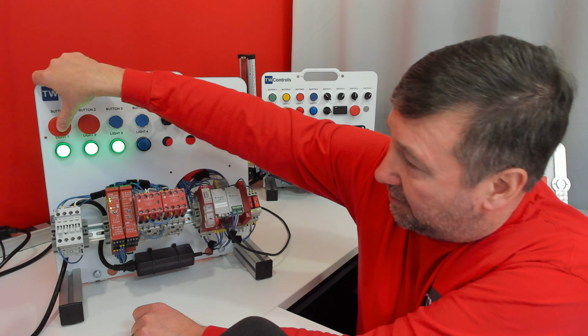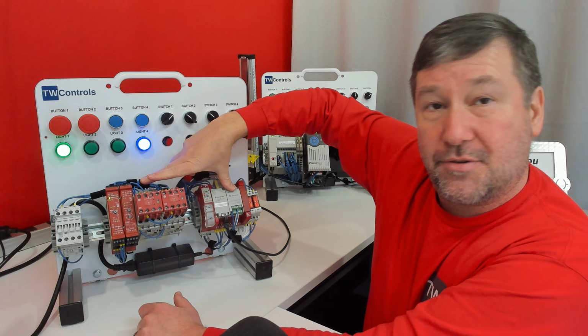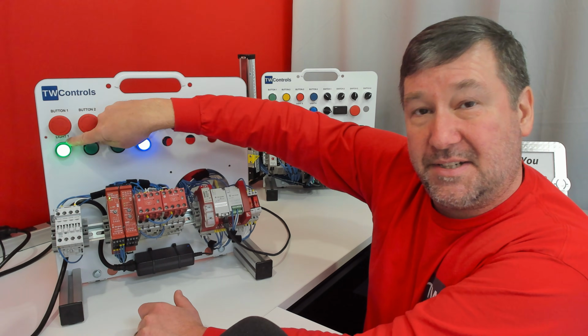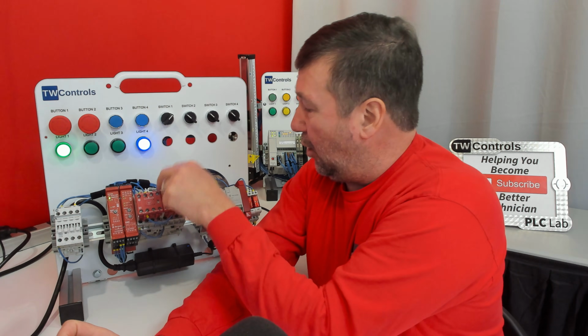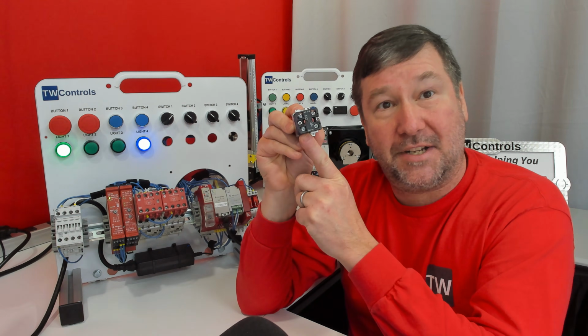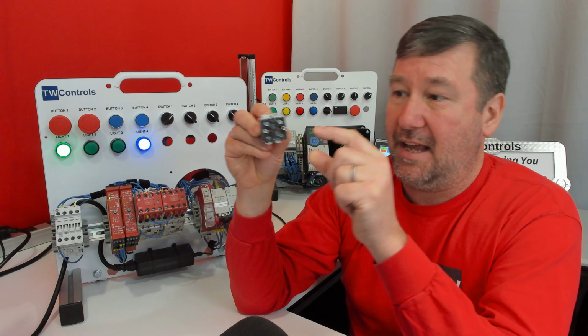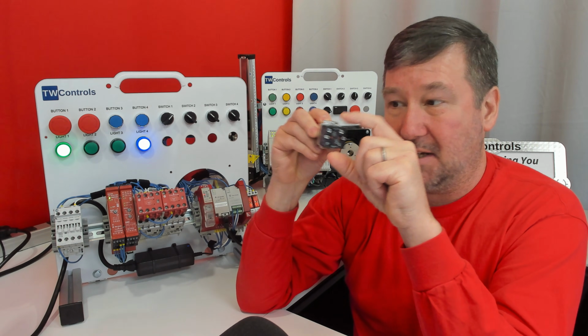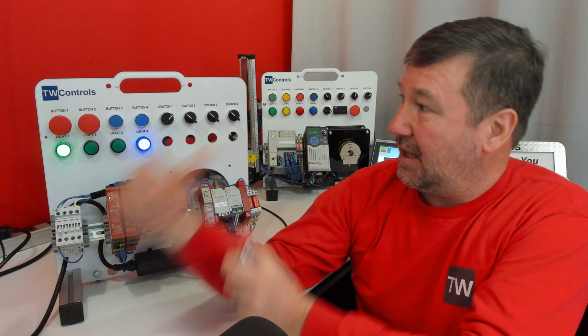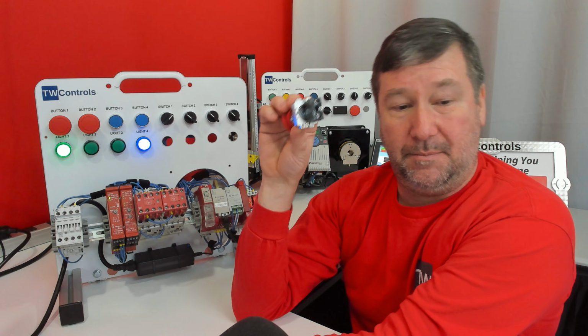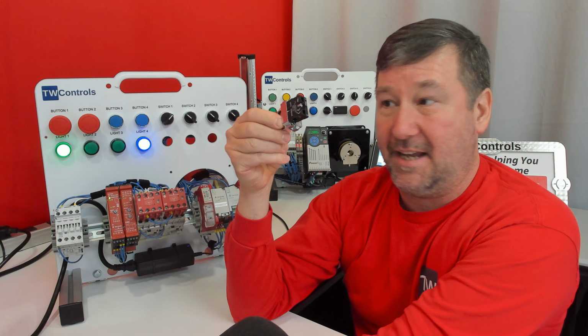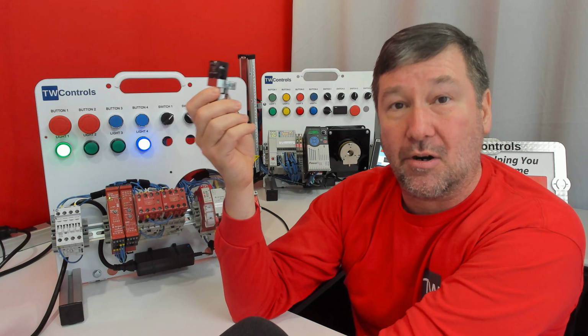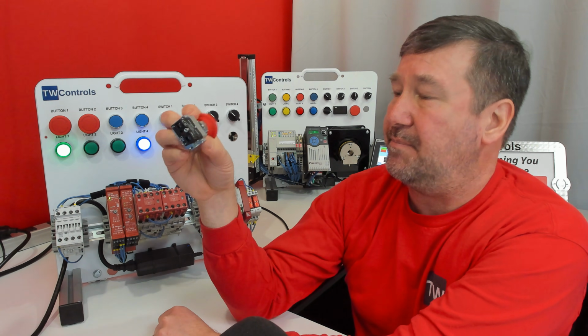And if we press our e-stop, notice these 2 drop out, but this one doesn't, because both of these have redundant contacts on the back of them. And even though one of them failed, it noticed it on the other one. This one right here is similar to this. And yeah, we had that single point failure, and now our operator is in harm's way.